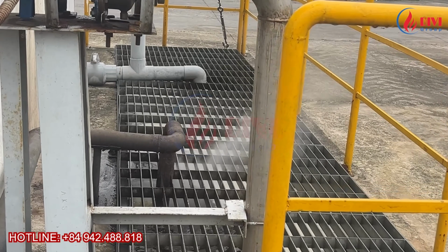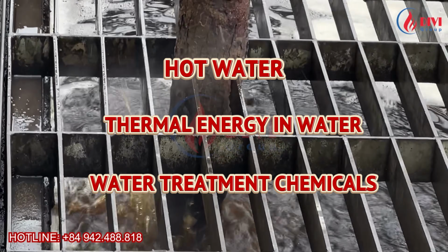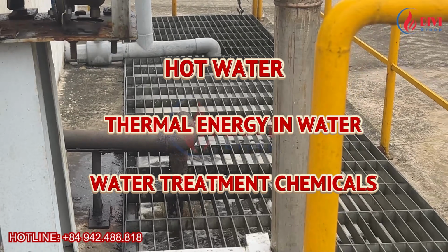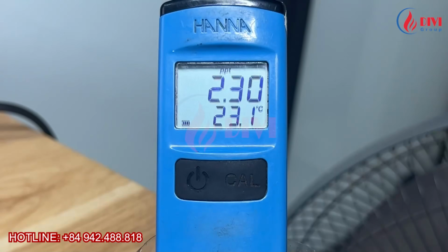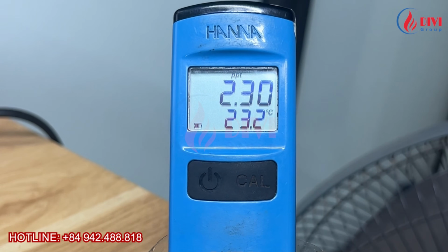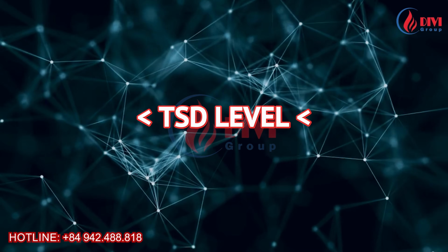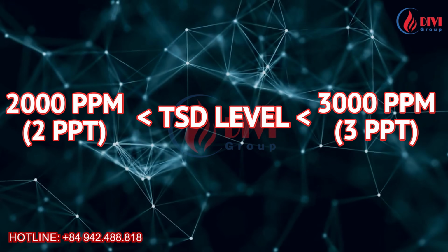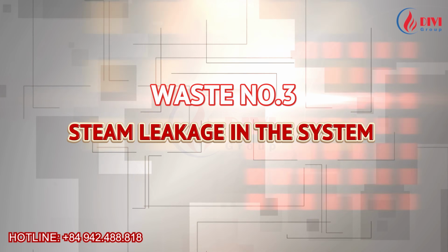Every blowdown releases hot water, thermal energy stored in the water, and water treatment chemicals. Without proper control, the system may lose hundreds of liters of hot water every hour, which translates into significant fuel loss. Therefore, blowdown should be calculated and controlled based on the boiler water TDS level, rather than done by guesswork or habit. Ideally, the TDS level in boiler blowdown water should be maintained between 2,000 to 3,000 ppm, or approximately 2 to 3 ppt.